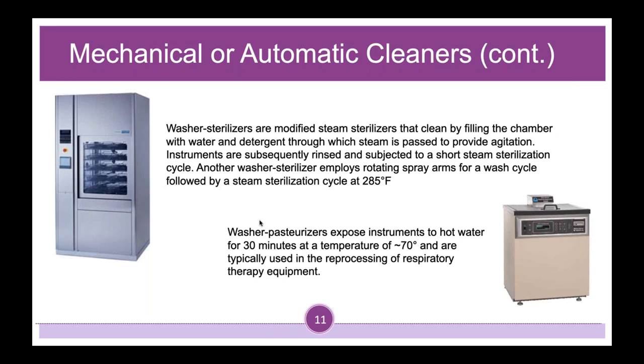Mechanical or automatic cleaners: washer sterilizers are modified steam sterilizers that clean by filling the chamber with water and detergent, through which steam is passed to provide agitation. Instruments are subsequently rinsed and subjected to a short steam sterilization cycle. Another washer sterilizer employs rotating spray arms for a wash cycle followed by a steam sterilization cycle at 285 degrees Fahrenheit. And then you've got your washer pasteurizers.